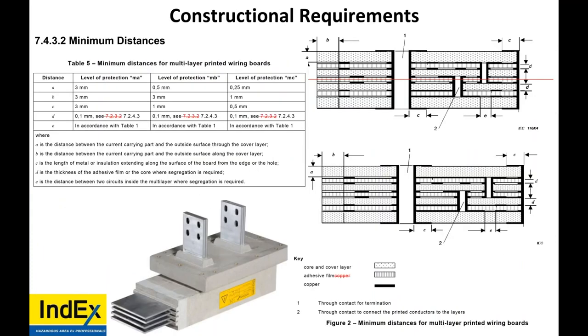Places such as Canada do not allow EXMA in a zone zero. They have their own national requirements. Pros and cons of using EXM over EXQ. Well, EXQ, I'm forgetting the maximum voltage, but EXM can be used in a zone zero. EXM, the encapsulant isn't going to leak out. EXQ, if it cracks open, the sand will leak out.